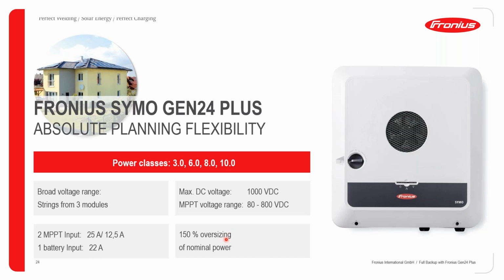Okay, with the Gen24 Plus, you can oversize it to 150%. So basically, if I purchase a 10 kilowatt Gen24 Plus inverter, I can put 15 kilowatts worth of PV panels. What it will ensure is that you can achieve a higher rate of production or a higher value of production throughout the day.